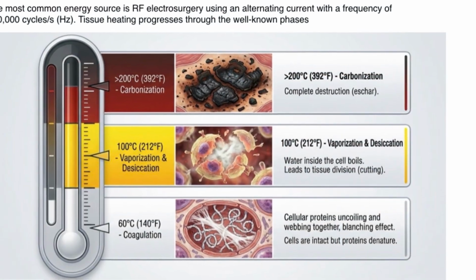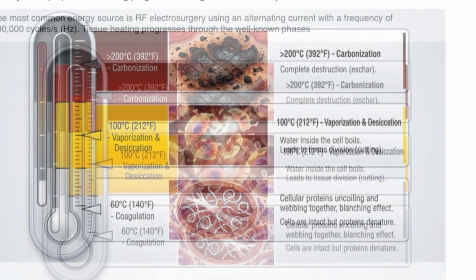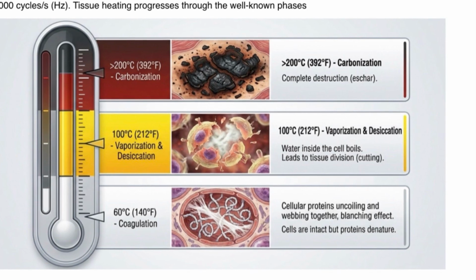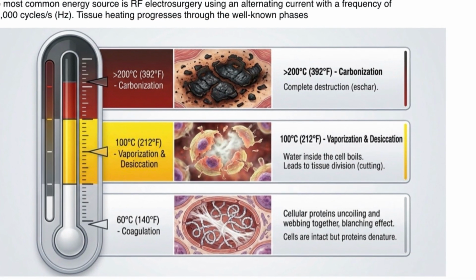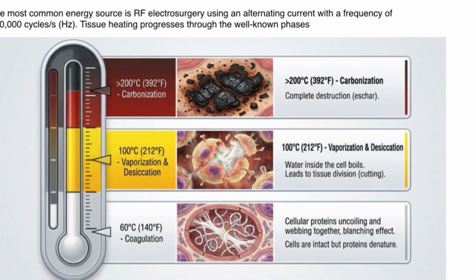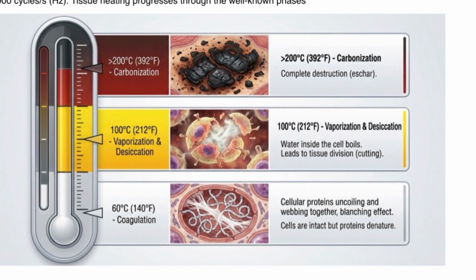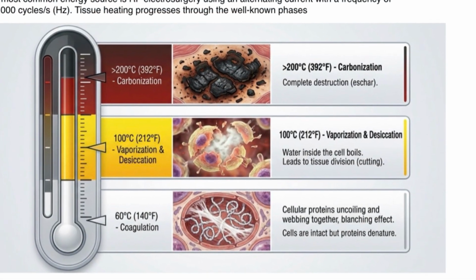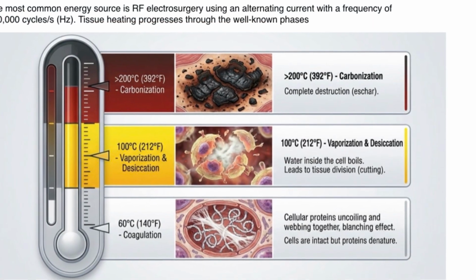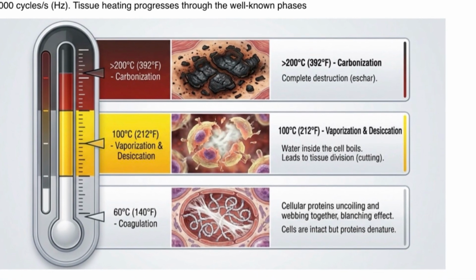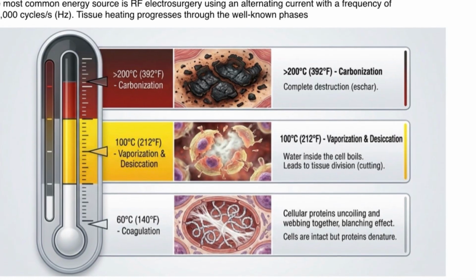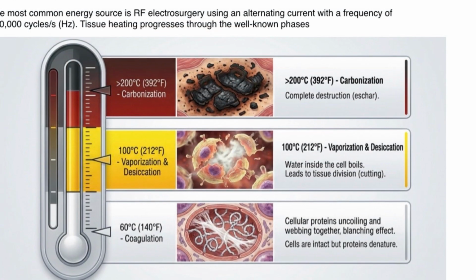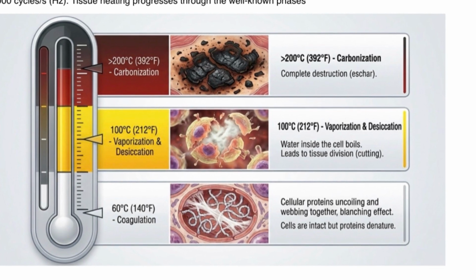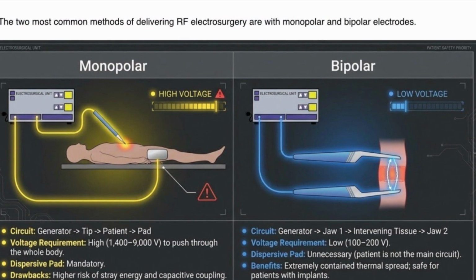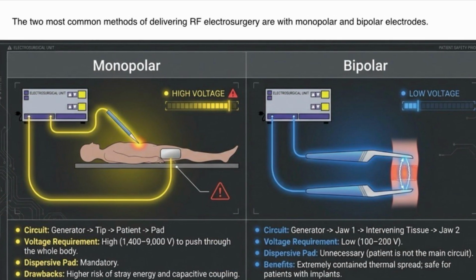So, the use of more than 10,000 Hz is mandatory to avoid neuromuscular stimulation. The most common energy source is radiofrequency electrosurgery, using an alternating current with a frequency of 5 lakh cycles per second. Tissue heating progresses through well-known phases. The first is the coagulation phase, where the temperature is around 60 degrees centigrade. The cellular proteins uncoil and web together, causing a blanching effect. Cells are intact but proteins denature. When the tissue temperature reaches 100 degrees centigrade, vaporization and desiccation occur. Water inside the cell boils, leading to tissue division, cutting. And when the temperature is more than 200 degrees centigrade, carbonization occurs. There is complete destruction.